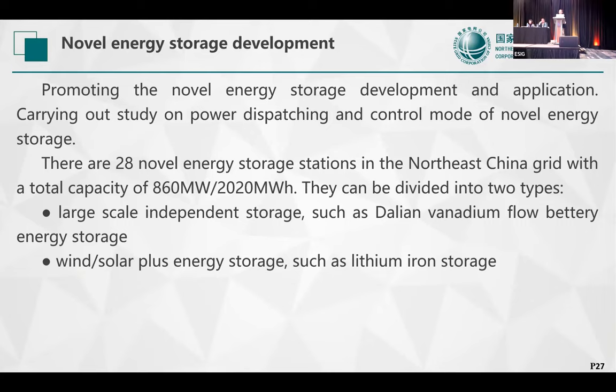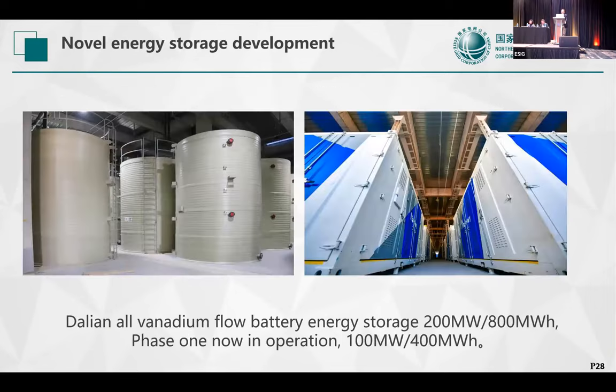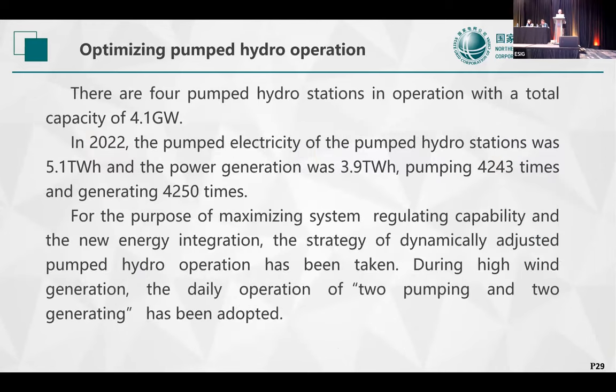Two types of the new energy storage. One is large scale independent storage. Another is wind solar plus energy storage. And this is the Dalian vanadium flow battery energy storage. The plant capacity is 200 megawatt and 800 megawatt hours. Phase one is now in operation, capacity is 100 megawatt or 400 megawatt hours.